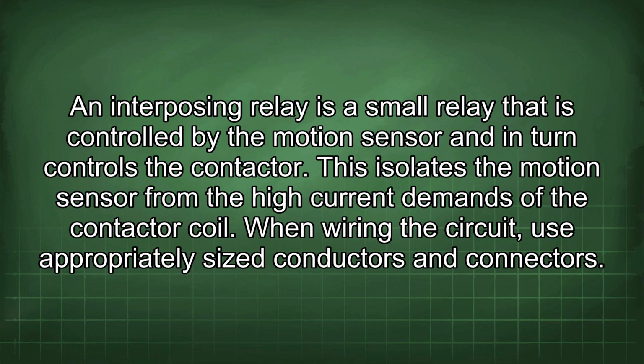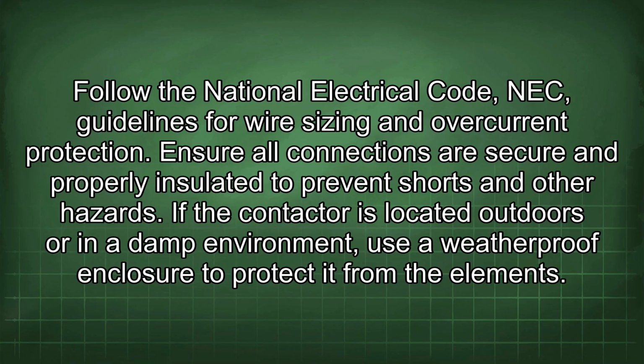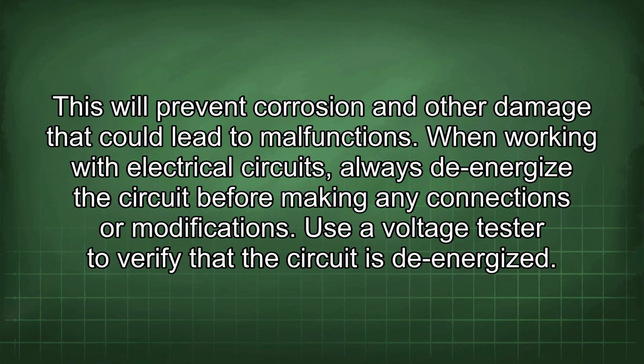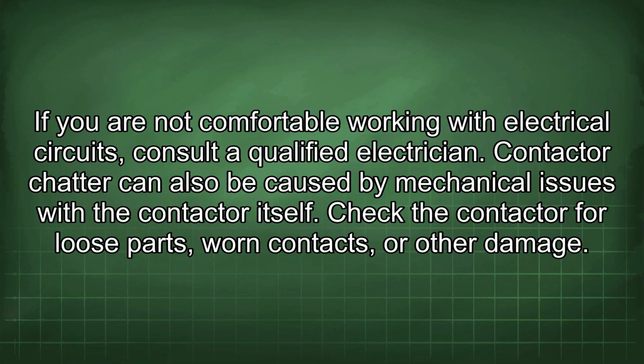When wiring the circuit, use appropriately sized conductors and connectors. Follow the National Electrical Code (NEC) guidelines for wire sizing and overcurrent protection. Ensure all connections are secure and properly insulated to prevent shorts and other hazards. If the contactor is located outdoors or in a damp environment, use a weatherproof enclosure to protect it from the elements. This will prevent corrosion and other damage that could lead to malfunctions. When working with electrical circuits, always de-energize the circuit before making any connections or modifications. Use a voltage tester to verify that the circuit is de-energized. If you are not comfortable working with electrical circuits, consult a qualified electrician.